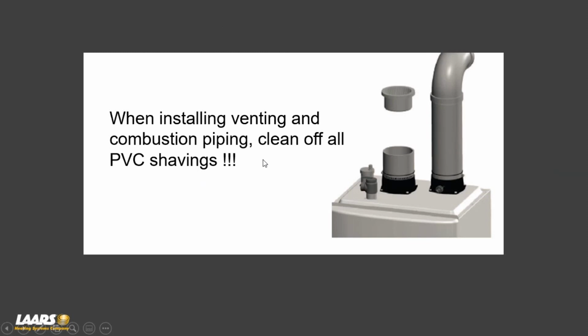Next, every manufacturer out there is running into PVC shavings in their burners, their blowers, what have you. Where's it coming from? During the installation, a lot of installers are using Sawzalls to cut your PVC pipe or CPVC pipe or whatever you utilize. And they're not wiping those shavings down. So where does that end up?